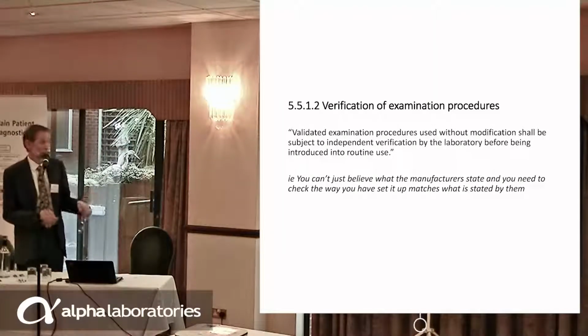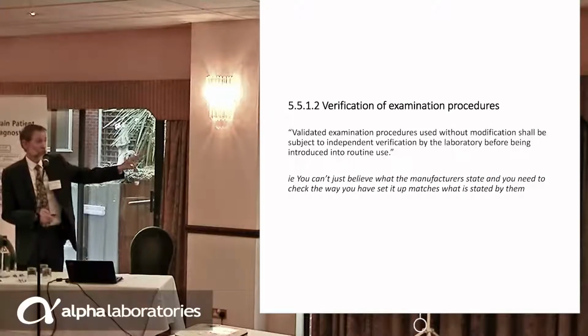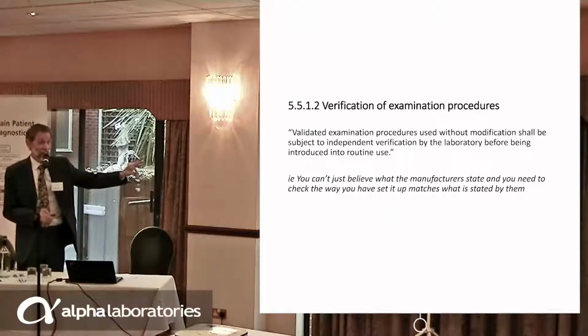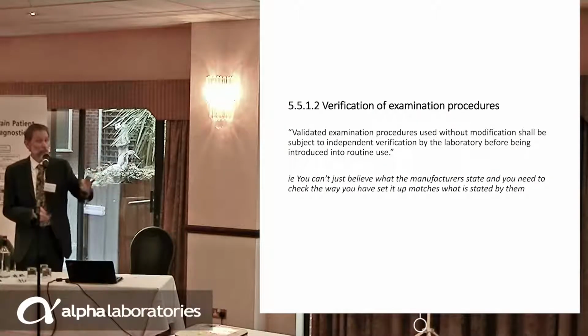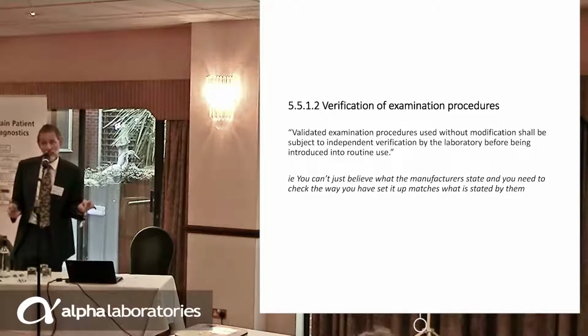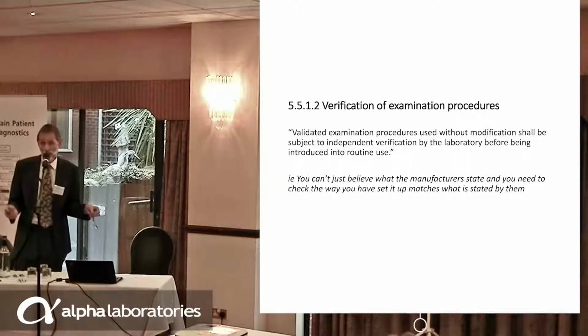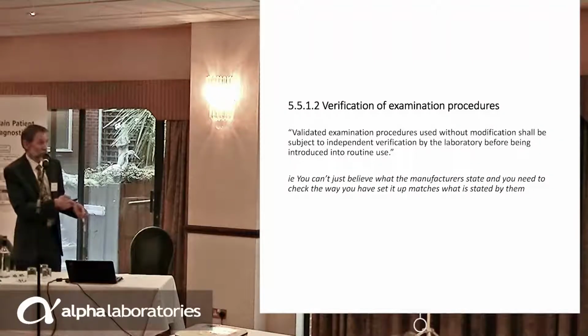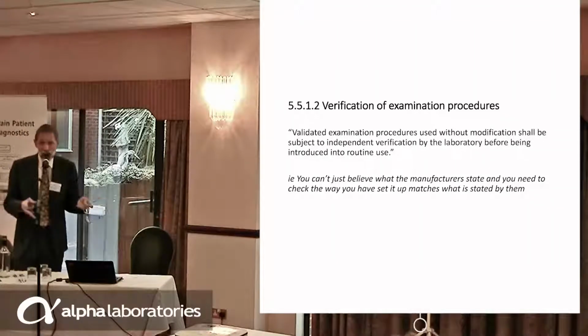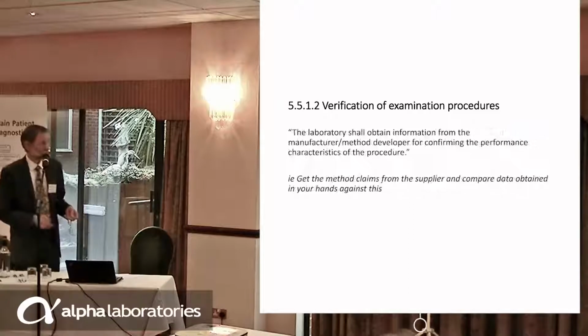the manufacturer's done it. So key thing here is you can't just believe what the manufacturers state, but equally you can't assume that the way you've set it up is going to be exactly the way the manufacturers have set it up. So for instance, a very simple mistake that can happen is you've got an endpoint chemistry on your general chemistry system and it requires you to plug a calibration value in. Okay, if you put that in wrong, you're going to have a bias, aren't you? So you're verifying that what you've done in terms of putting everything together is working correctly.